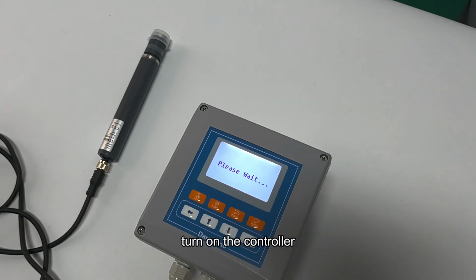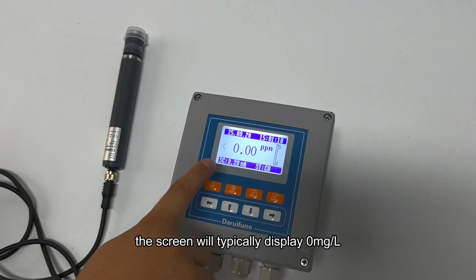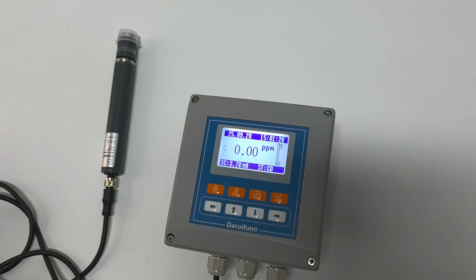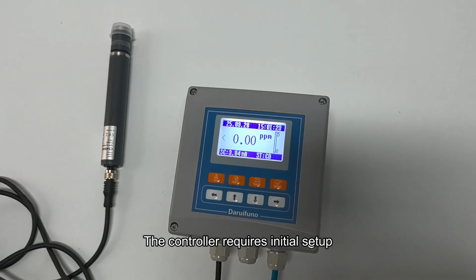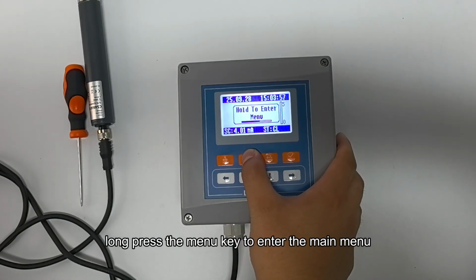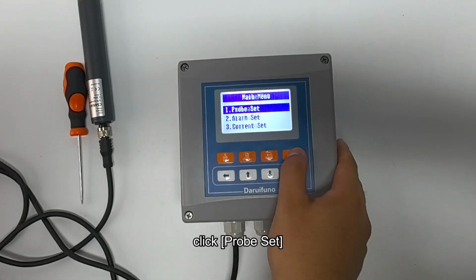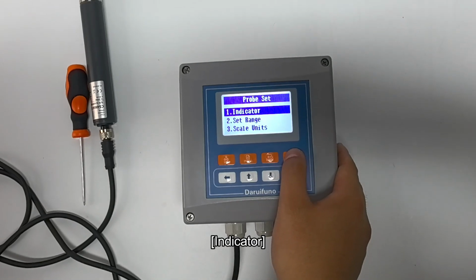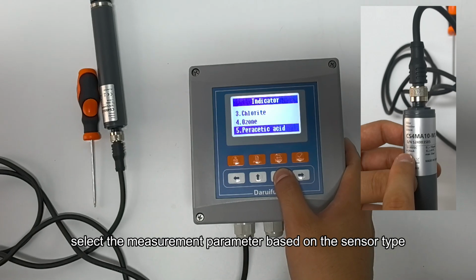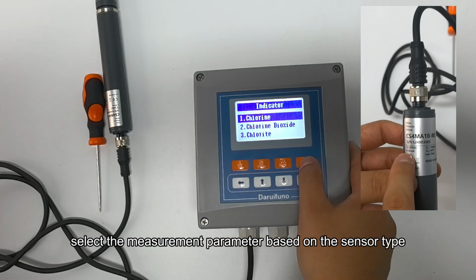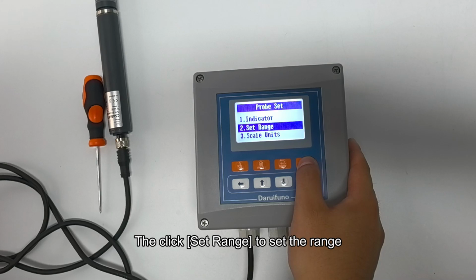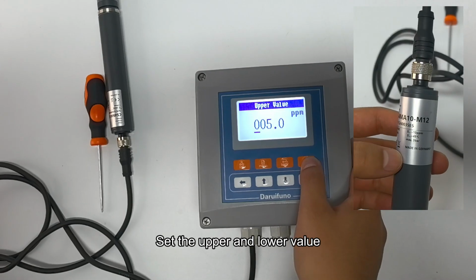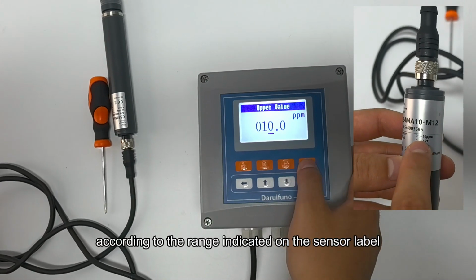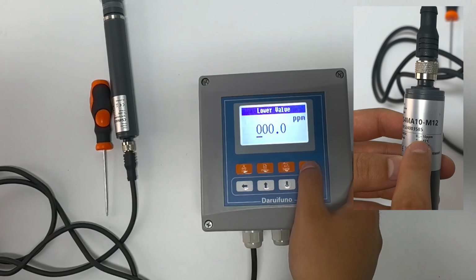Turn on the controller. The screen will typically display 0 mg per liter. The controller requires initial setup. Long press the menu key to enter the main menu. Click Probe Set, Indicator. Select the measurement parameter based on the sensor type. Then click Set Range to set the range. Set the upper and lower value according to the range indicated on the sensor label.